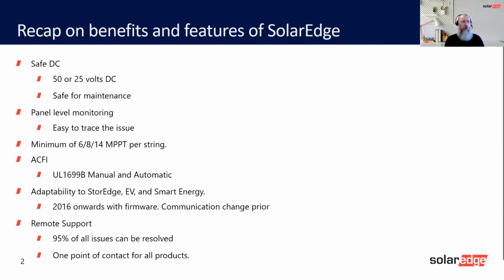I've already spoken about arc fault circuit interruption, but there's only one standard at the moment. There's another standard, an IEC standard, which is in draft form, but that's not released yet. That's only draft. So this is the only standard the world has at the moment for arc fault circuit interruption. And it's an American standard, a North American standard. As I said, the IEC is in draft.